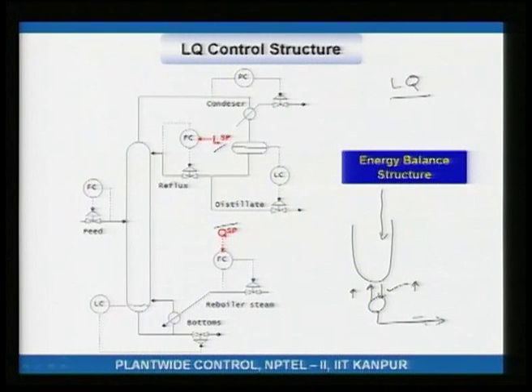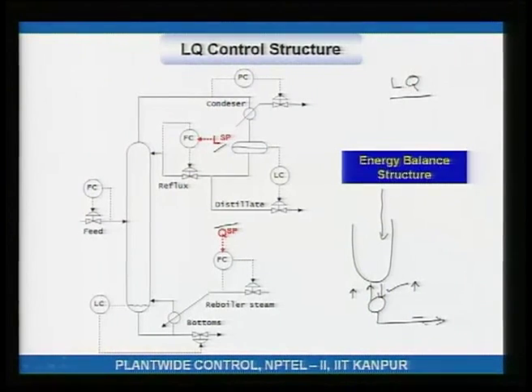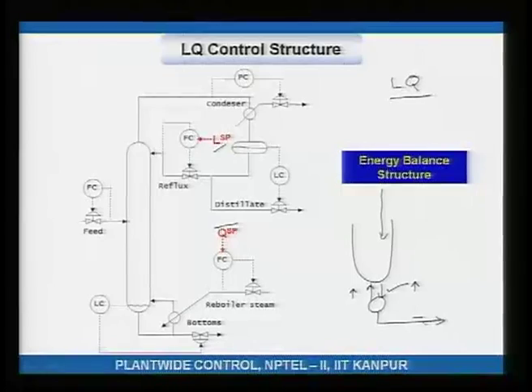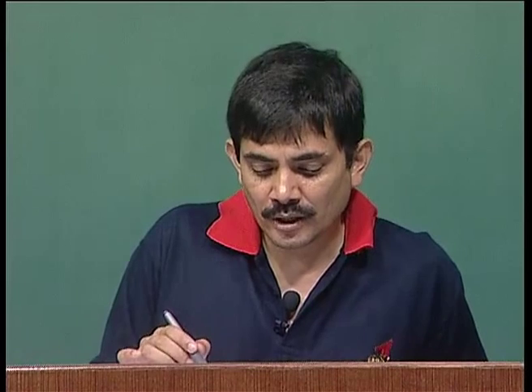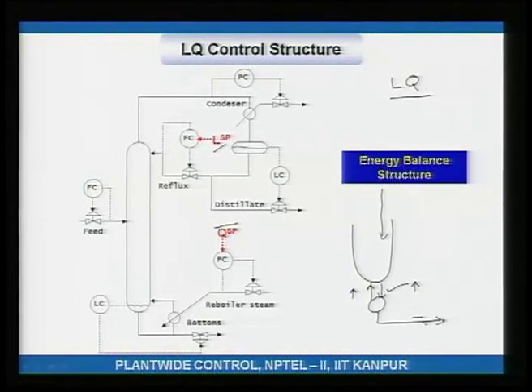The LQ structure and its derivatives are the most commonly used control structures for distillation columns. It is the reflux and reboil that provide the flashing on the trays. Without reboil, the stripping section trays are essentially pure liquid; without reflux, there is no liquid in the enriching section and no flashing occurs there.